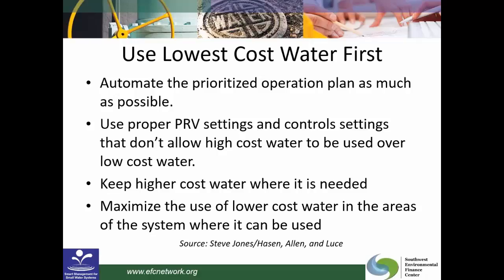Make sure that your PRV settings, your control settings, and the set points in your tanks are not causing you to use your high cost water over low cost water. Keep your high cost water where it's needed, and maximize the use of the lower cost water in the areas of the system where it can be used. So if you have multiple pressure zones, and you are pumping water up to a storage tank with a high lift pump, maybe not everybody needs to have water from the tank. Maybe some of the water could come from the wells directly for the people that are at lower elevations. These are the kinds of things that we're wanting you to look at and consider.